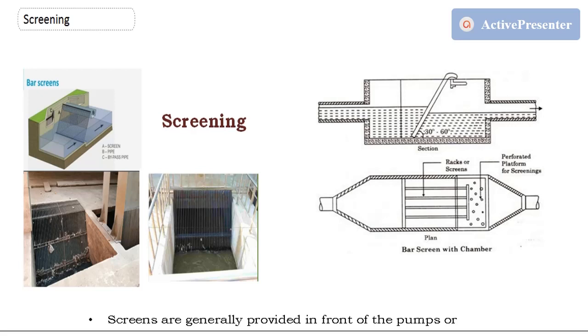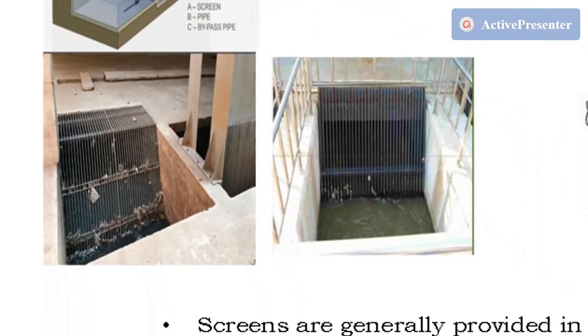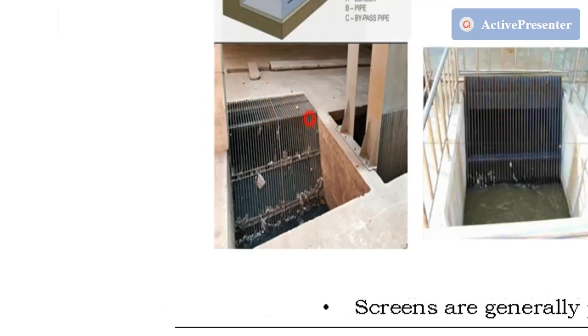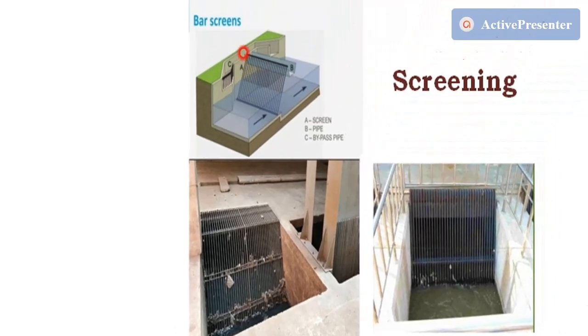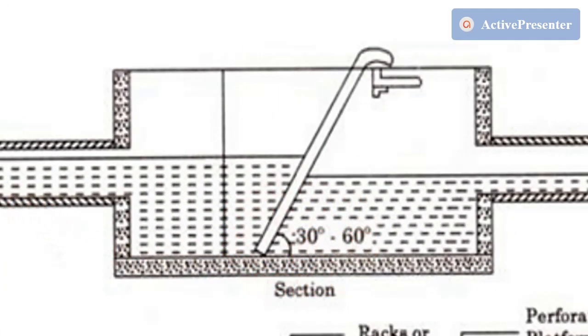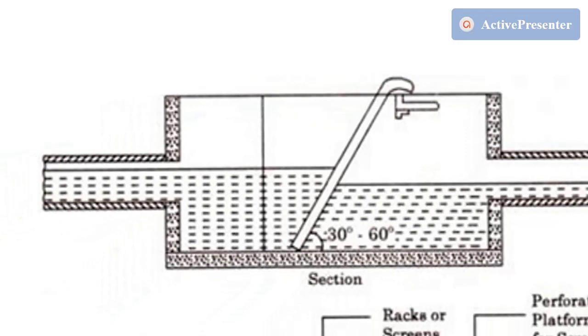These large materials need to be removed — this process is not filtration, you are simply removing them. Therefore we use screens. The screens are made of vertical bars; as you can see in the actual picture, vertical bars are there and they may be inclined at 30 or 60 degrees, or purely vertical. In this animation figure the inclined screen is shown. Water flows through, and materials larger than the screen opening settle out while clean water passes.